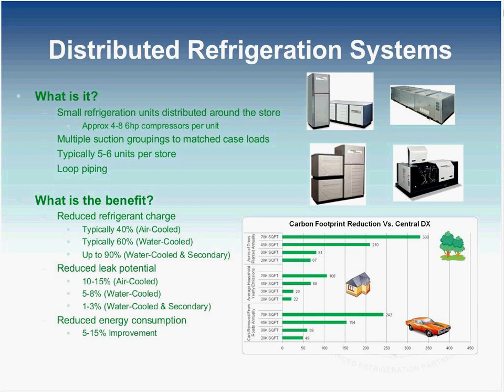So a lot of benefit in terms of charge reduction that you can get from a distributed system. And along with that, if you reduce your charge and you have brazed joints and your equipment's located closer to your loads, you can reduce the number of fittings in the store and reduce your leak rates as well.